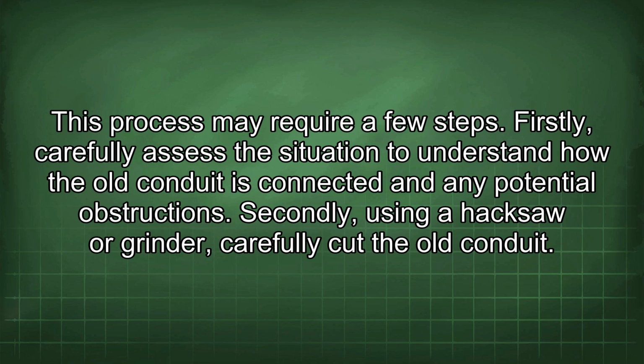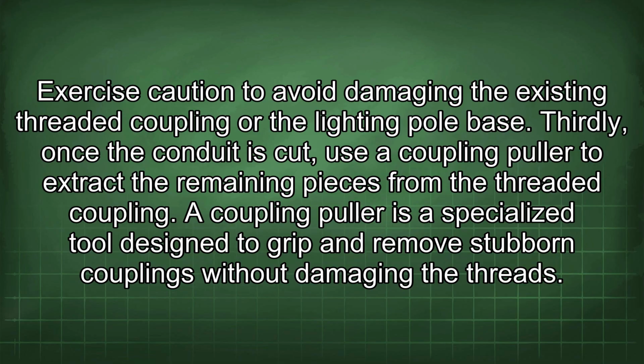Firstly, carefully assess the situation to understand how the old conduit is connected and any potential obstructions. Secondly, using a hacksaw or grinder, carefully cut the old conduit. Exercise caution to avoid damaging the existing threaded coupling or the lighting pole base. Thirdly, once the conduit is cut, use a coupling puller to extract the remaining pieces from the threaded coupling. A coupling puller is a specialized tool designed to grip and remove stubborn couplings without damaging the threads.